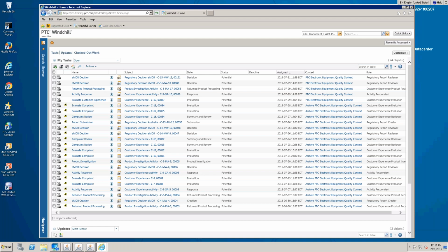move forward with that. Once again, if it needs to be a design change because it's something that is reoccurring at a certain stage, or once again, it may be a one-off, then we can go through and do that. But also remember that we also have the CAPAs that we can go through and use. So in conjunction with the information that we have here, if that was something that was an issue, we can now go in and create a CAPA for it, and then actually associate that CAPA to this as well.